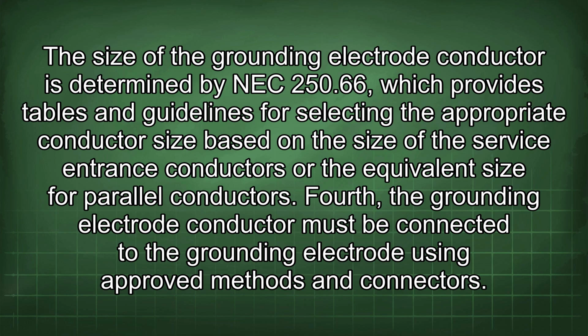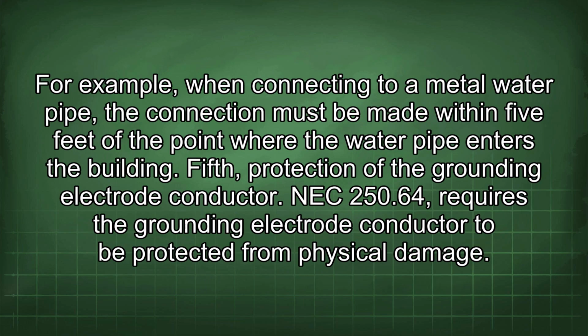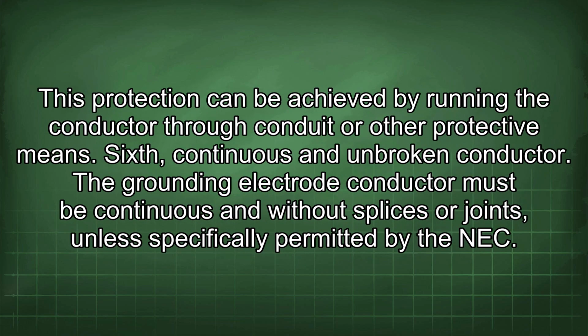Fourth, the grounding electrode conductor must be connected to the grounding electrode using approved methods and connectors. For example, when connecting to a metal water pipe, the connection must be made within 5 feet of the point where the water pipe enters the building. Fifth, protection of the grounding electrode conductor. NEC 250.64 requires the grounding electrode conductor to be protected from physical damage. This protection can be achieved by running the conductor through conduit or other protective means.